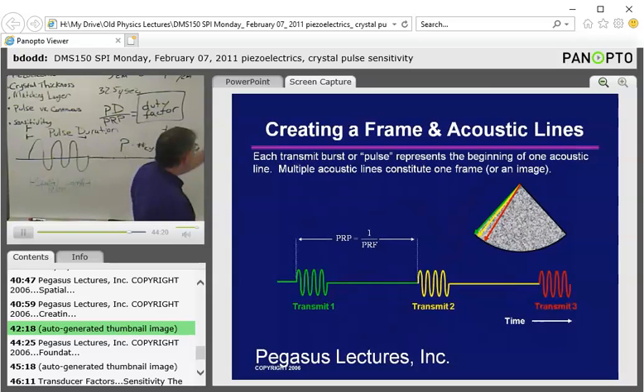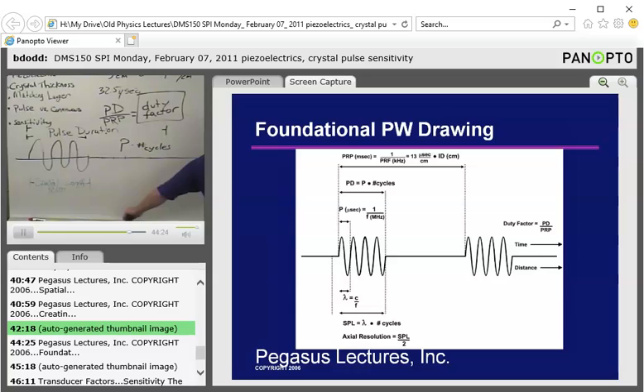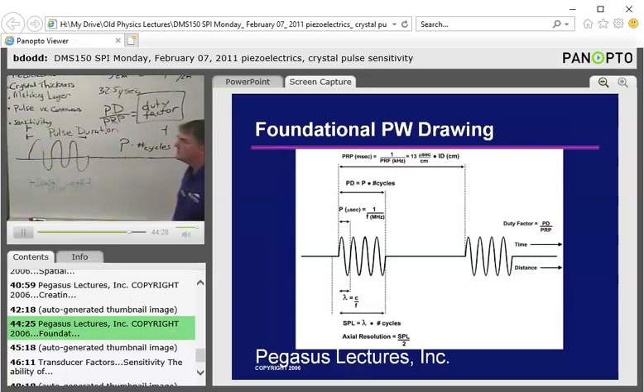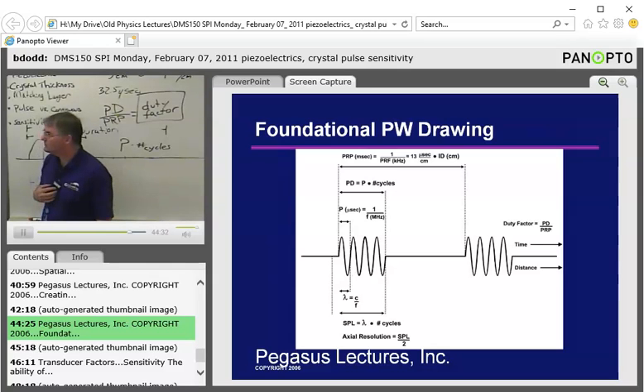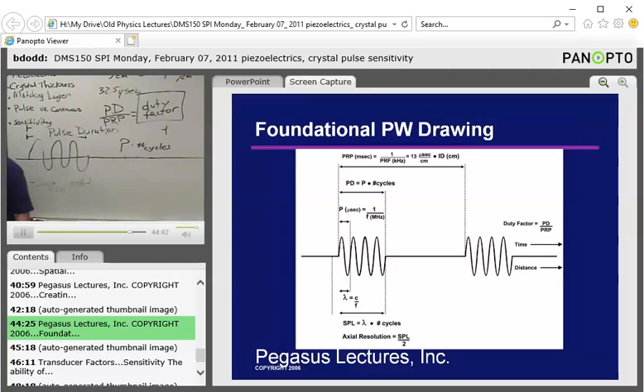Okay. So now we've talked all about pulse wave imaging. This is kind of your drawing that we're going to be creating over the next few weeks. A period is the length of one cycle, the length in time. The length in space of one cycle is the wavelength. The wavelength we can calculate, it's C over F. Period is 1 over frequency. Pulse duration is equal to the period times the number of cycles. Spatial pulse length is the wavelength times the number of cycles, so they're very equivalent. You can see they're just drawn in different domains. We have the time domain and we have the distance domain here. Our duty factor is defined as the pulse duration divided by the pulse repetition period.